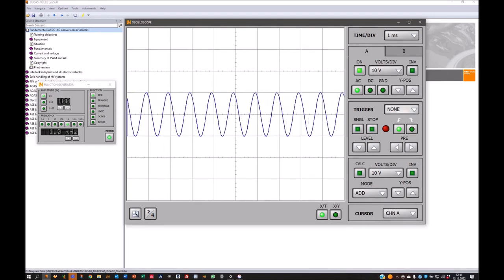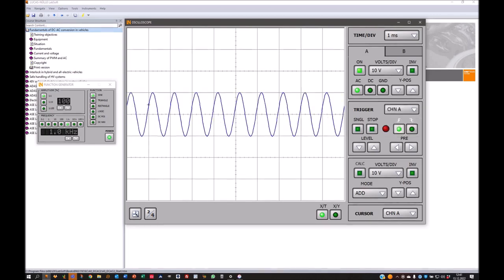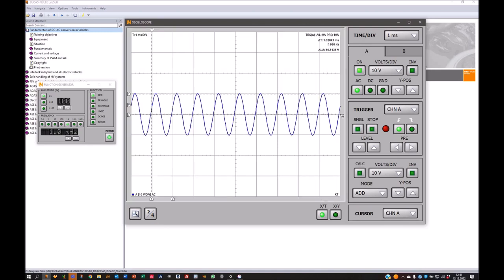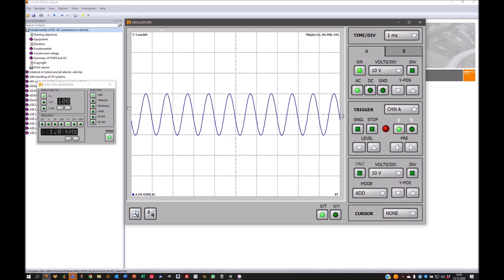Let's come now to the trigger. When we come to channel A, you see now this black crossover here. When we switch to that view, it will change and you will have T. This is what you see here. T, T. We remove the cursor for now. So this is just the trigger now where you can now change the X and the Y position.